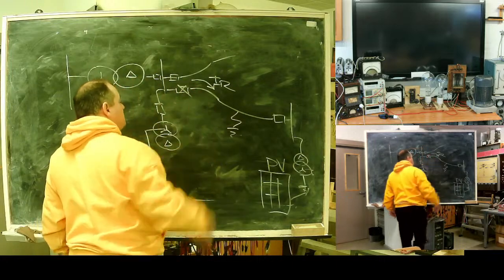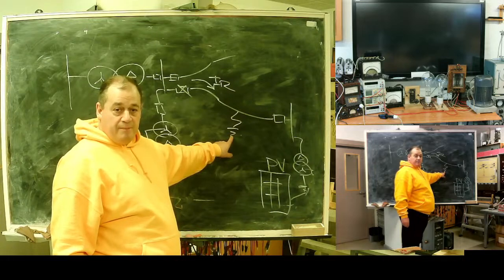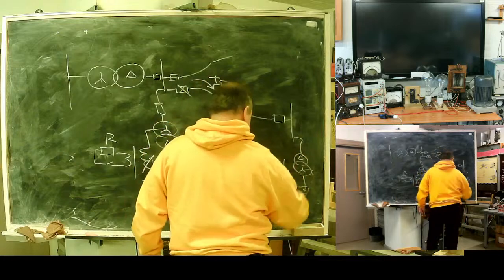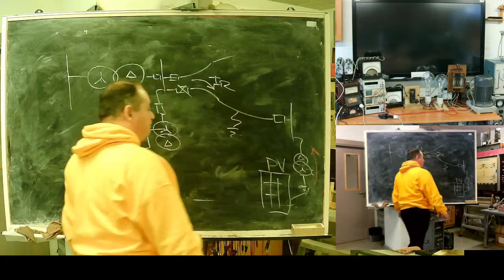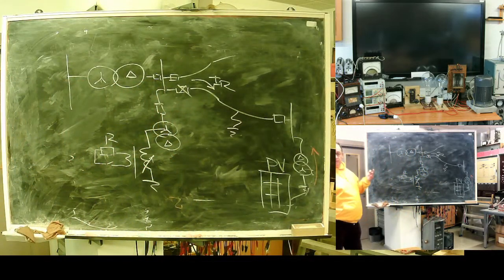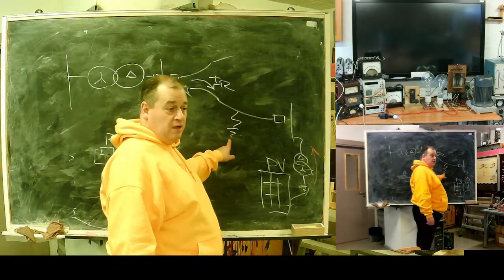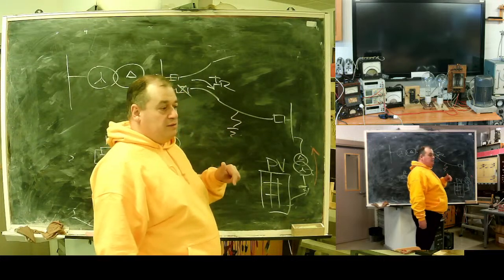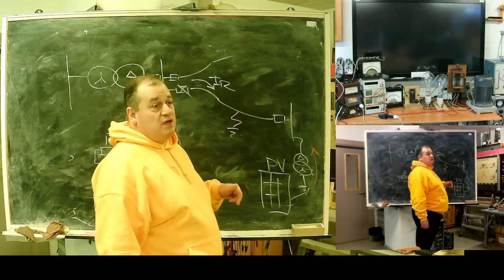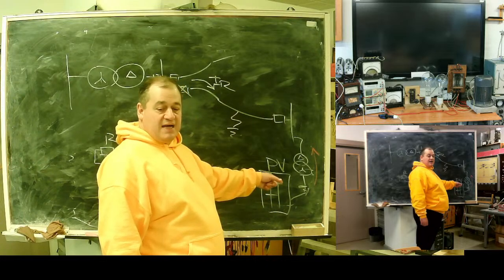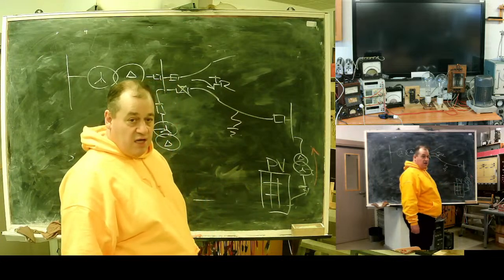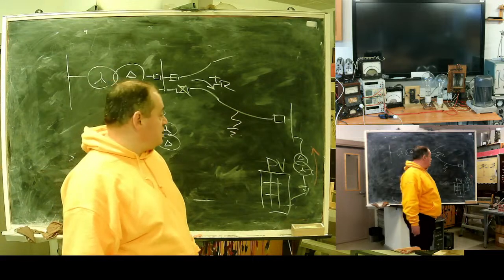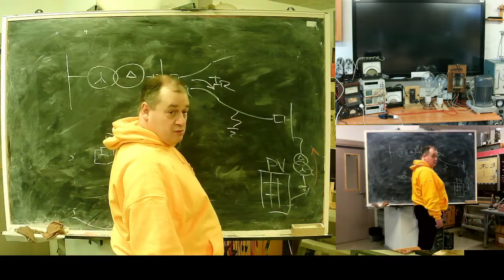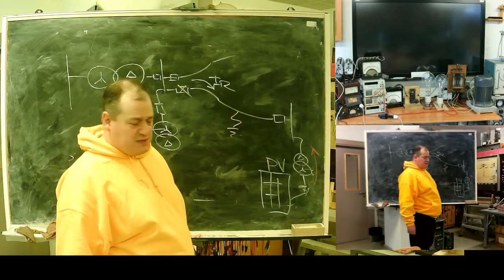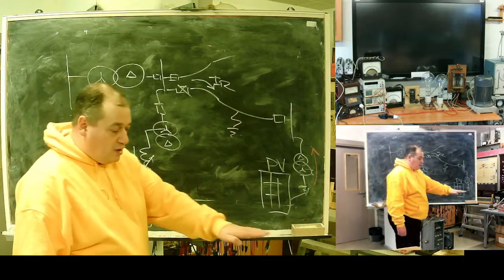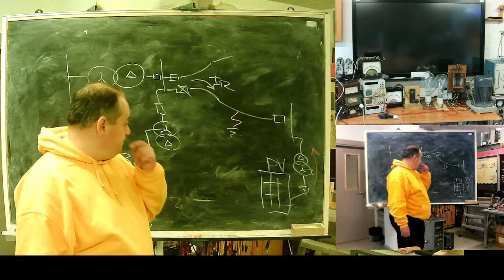Whoa. If this relay disconnects, will voltage disappear? No. We will still receive energy from this photovoltaics through back transformation, and the fault will be energized. Is this problem solved at this moment? It's not solved. Actually, if we have a large customer park, they are required to disconnect the inverter. They are forbidden from island operation. They should discontinue supply if connection is lost. It can be determined by frequency shift. But for small ones, no guarantee.